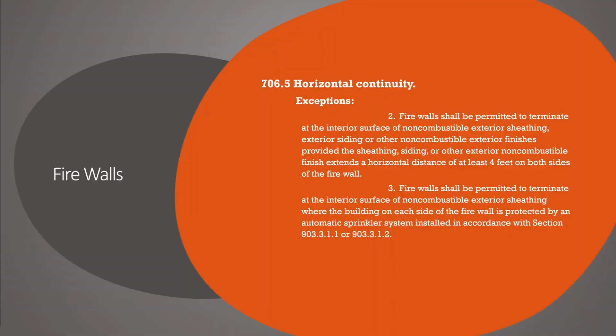And then for the exterior walls, where the firewall intersects exterior walls, the fire resistance rating and opening protection of exterior walls shall comply with one of the following. Not all of them, just pick one. 1, the exterior walls on both sides of the firewall shall have a 1 hour fire resistance rating with 3/4 hour protection, where opening protection is required by 705.8. 705.8 is the section for exterior walls. The fire resistance rating of the exterior wall shall extend a minimum of 4 feet on each side of the intersection of the firewall to exterior wall.